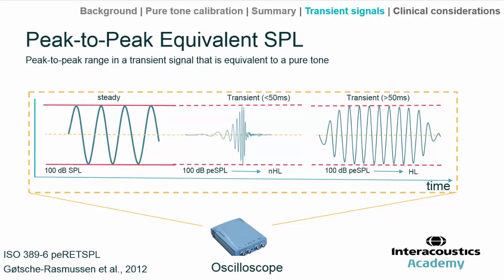An audiological instrument calibrated to reference thresholds using the peak-to-peak equivalent sound pressure level — often abbreviated just to peak-equivalent — is denoted by the use of NHL. Traditionally, NHL meant that references were being used — reference equivalent threshold sound pressure levels — that hadn't in fact been published in international standards, so perhaps locally derived references. But we now have an international standard, ISO 389-6, for a series of transients in common use: tone bursts, clicks, and so on.